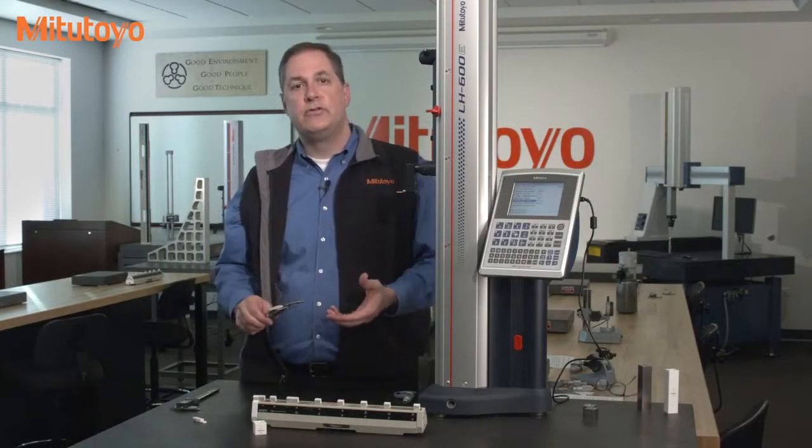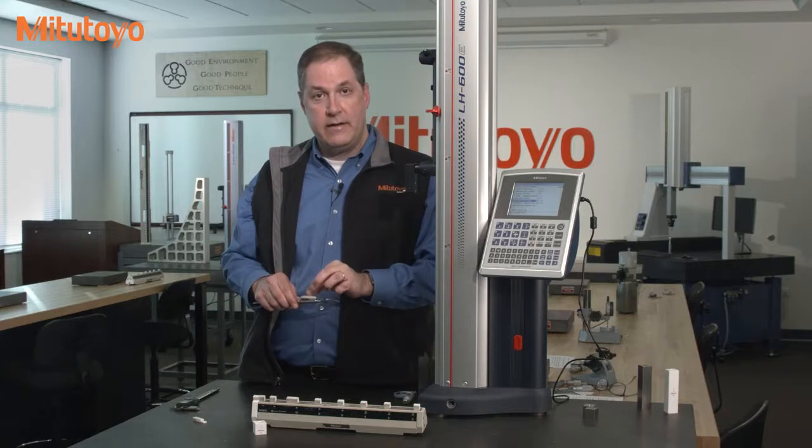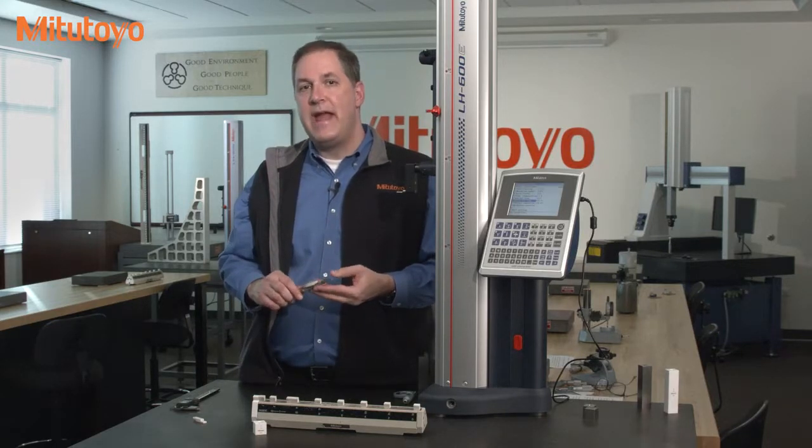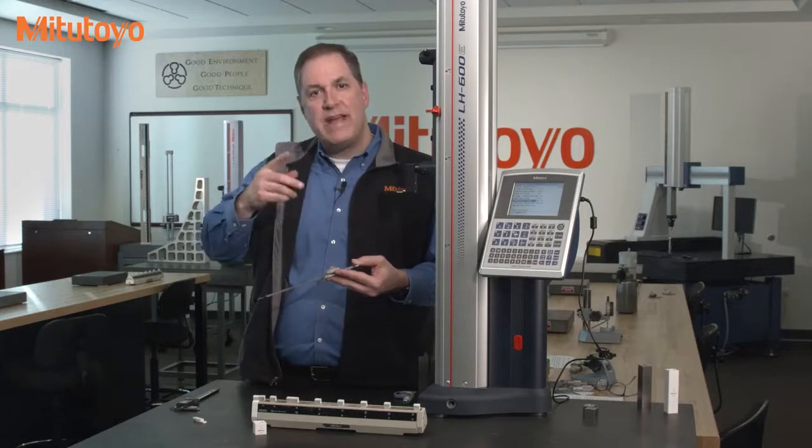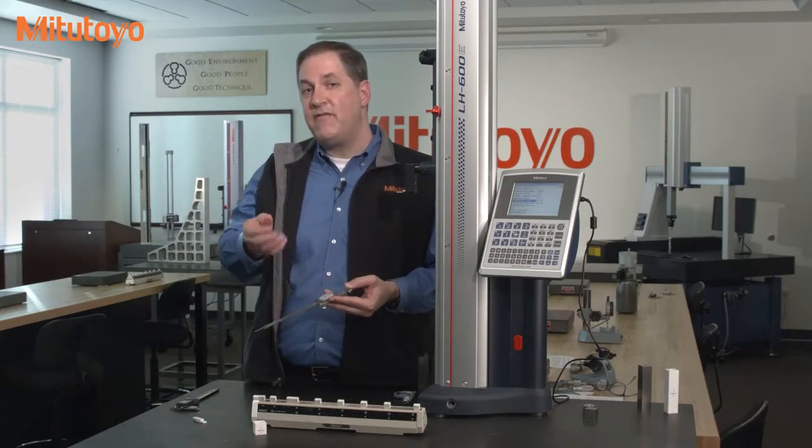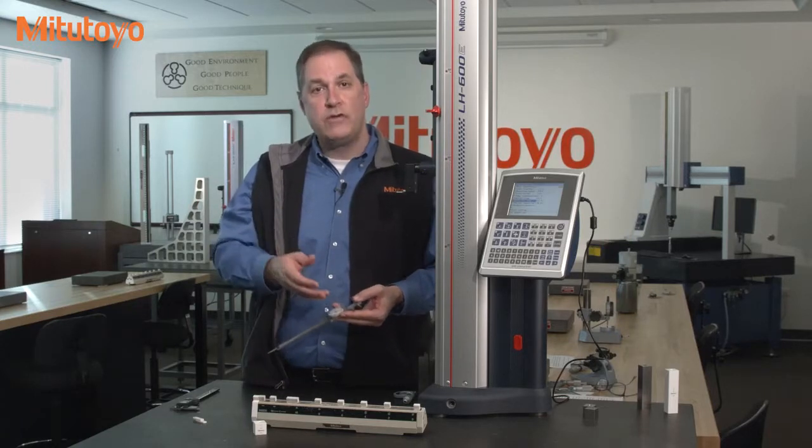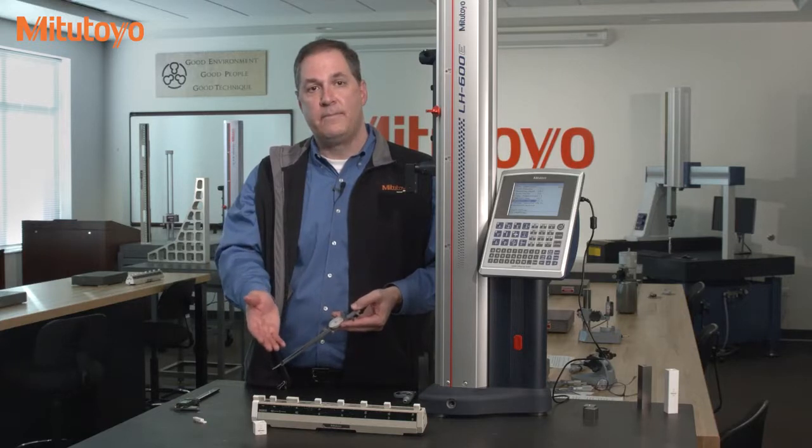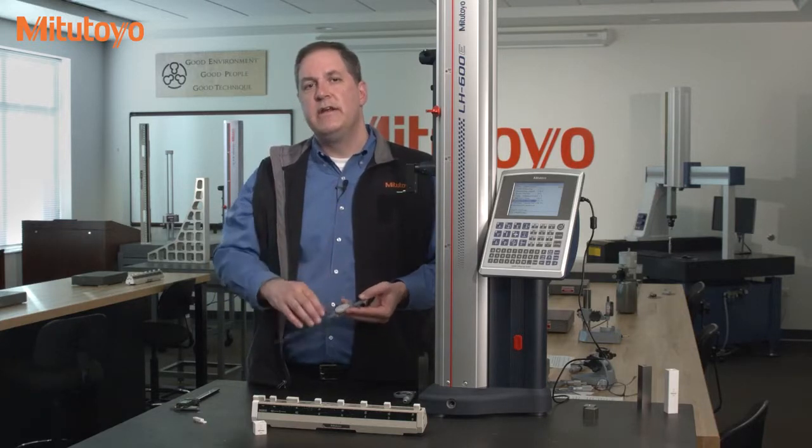Now dial calipers use little gears inside and the gears can wear. It's possible for there to be errors within a rotation of the dial that you won't see if the calibration method results in the pointer always being at the 12 o'clock position like you just saw.